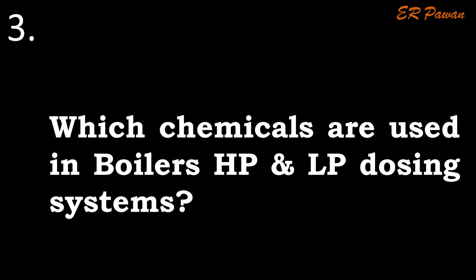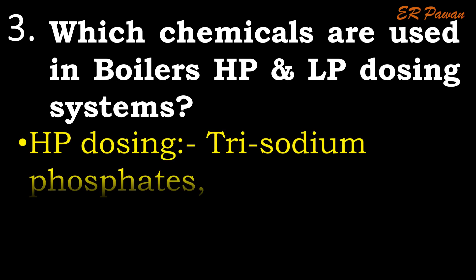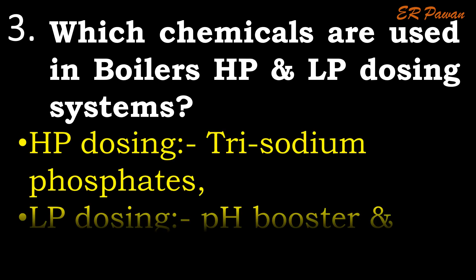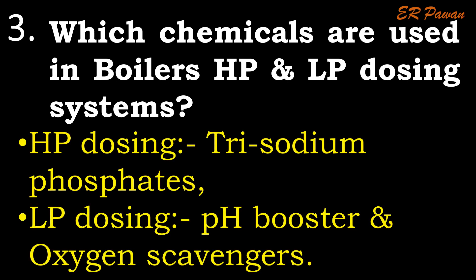Question 3: Which chemicals are used in boilers' high pressure and low pressure dosing systems? For high pressure dosing: trisodium phosphate. And for low pressure dosing: pH booster and oxygen scavengers.